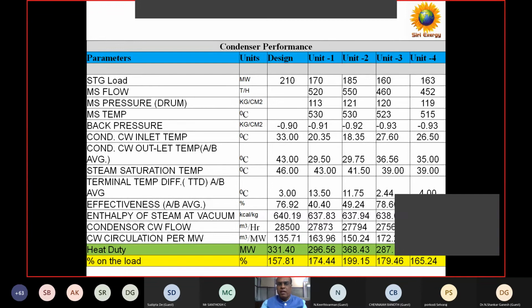That's why we are taking the audit on an as-run basis. Whatever load they are running, we take the data, analyze it, and give the results. Just for design purpose, at the design stage, I'll give an example. We have a typical heat duty of the condenser - this is almost condenser A and B. So here I calculated, for this 210 megawatt unit, we are dumping heat duty equivalent to almost 331.4 megawatt.